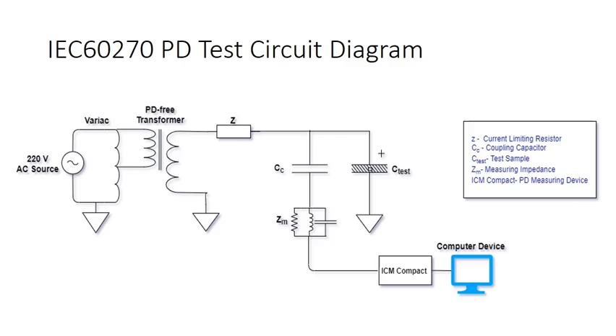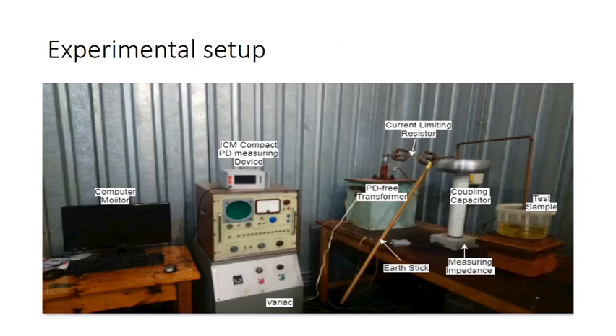This circuit represents the standard partial discharge test circuit. This is the practical experimental setup used for partial discharge measurement in the high voltage laboratory. The voltage is slowly increased using the variac until partial discharges are observed in the partial discharge measuring device. The results are then stored in the computer for further analysis.